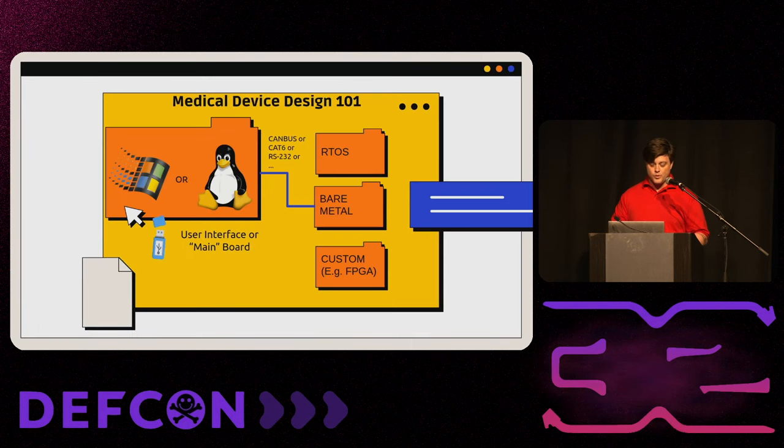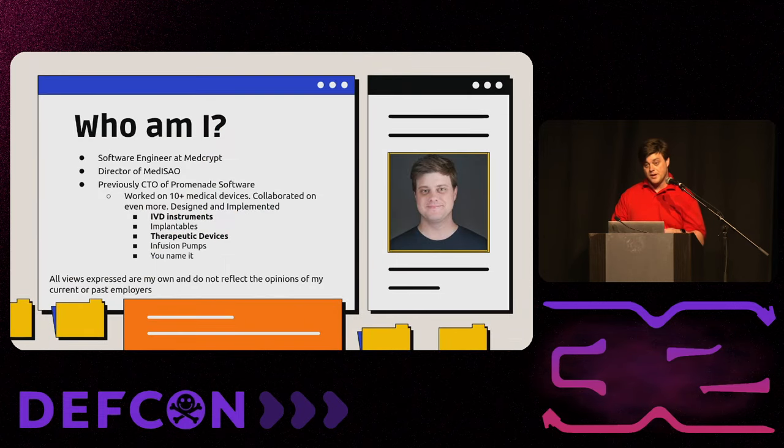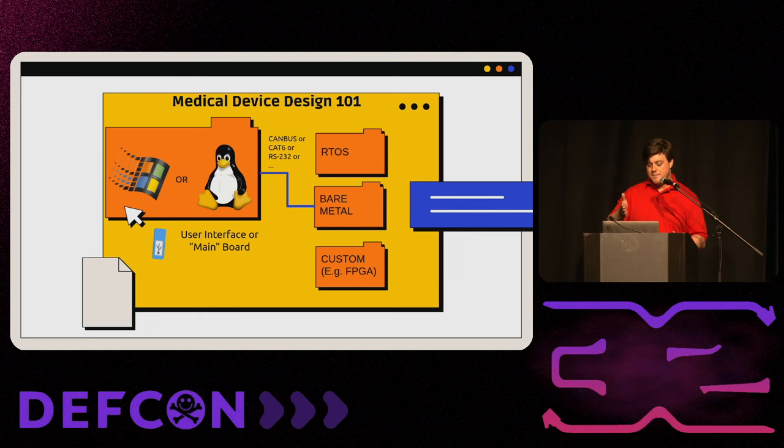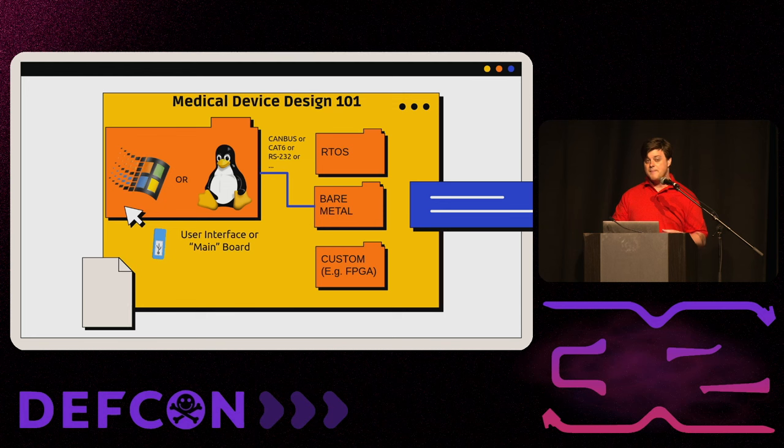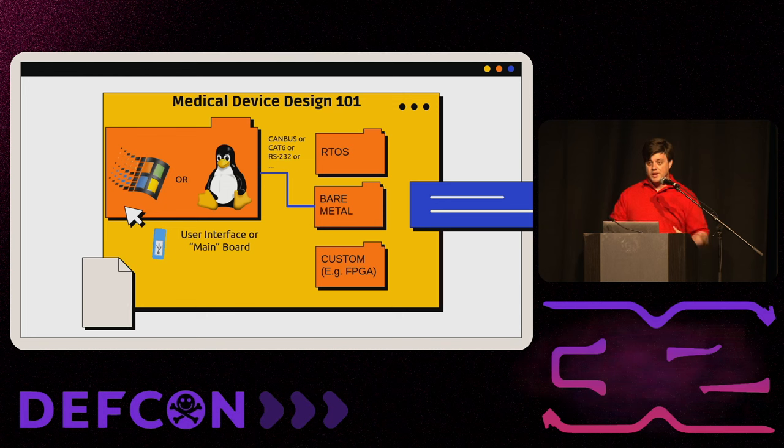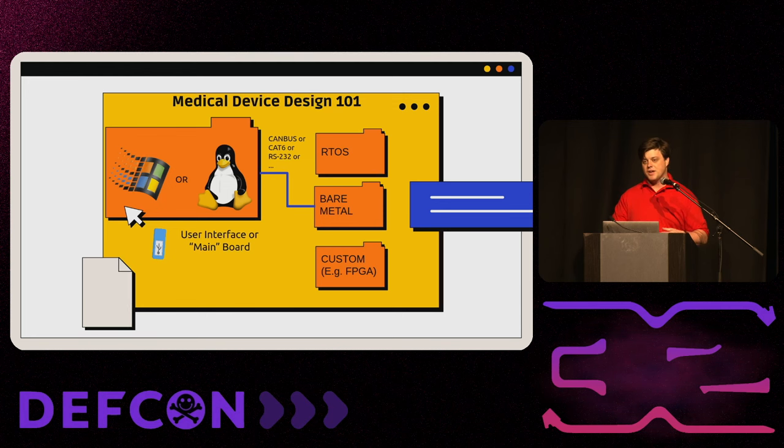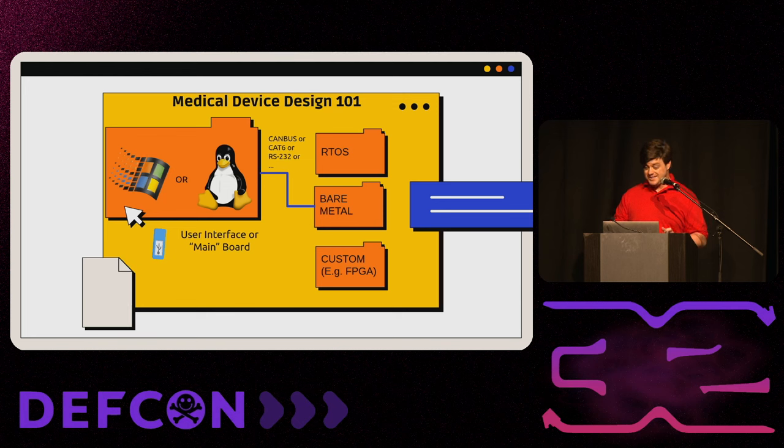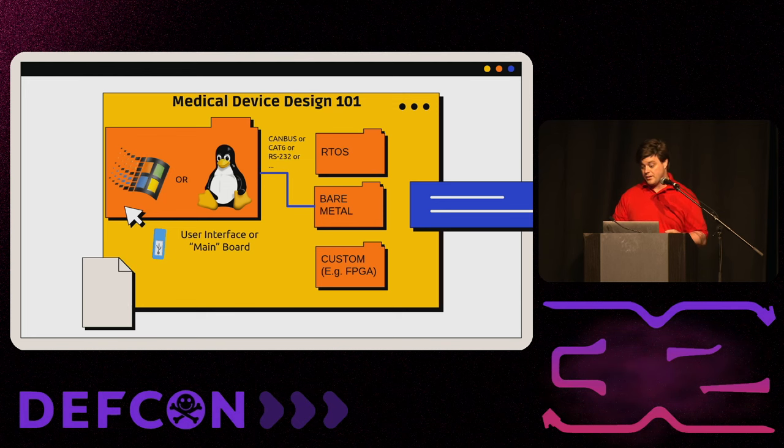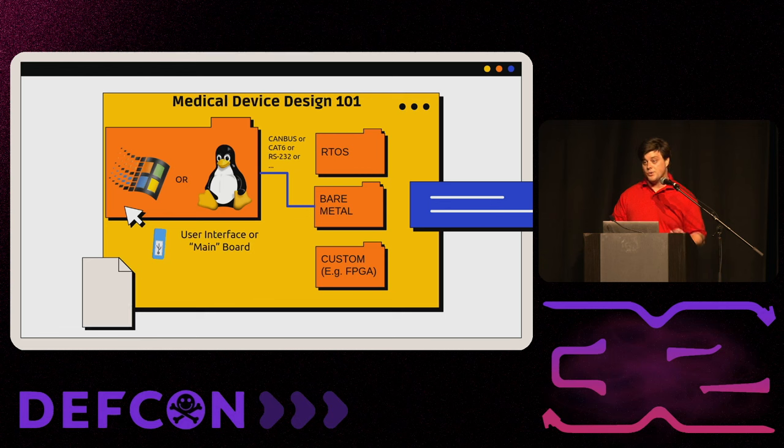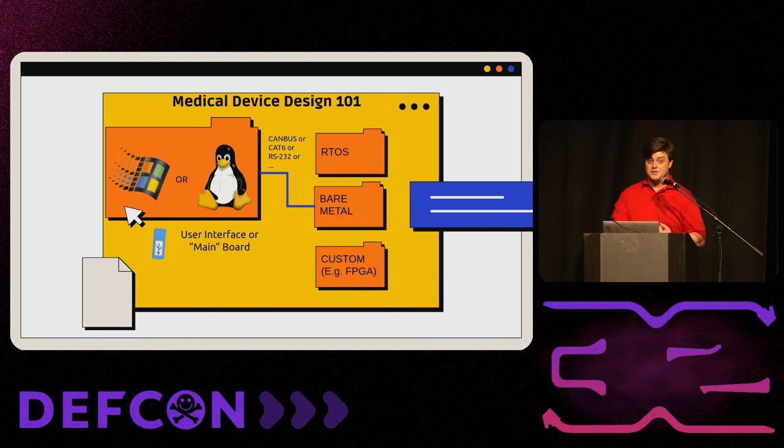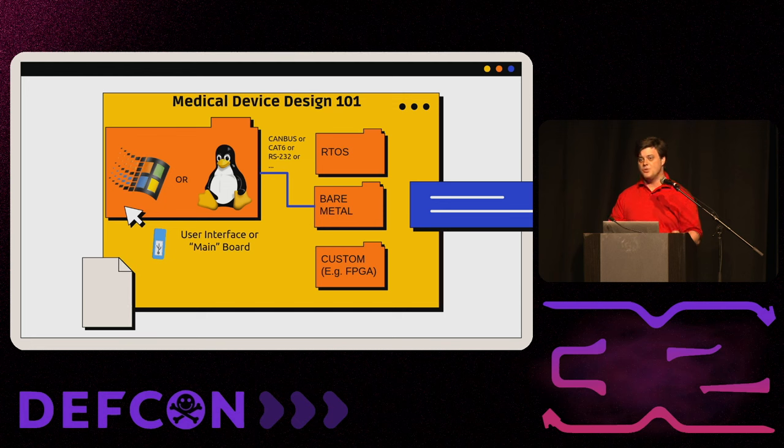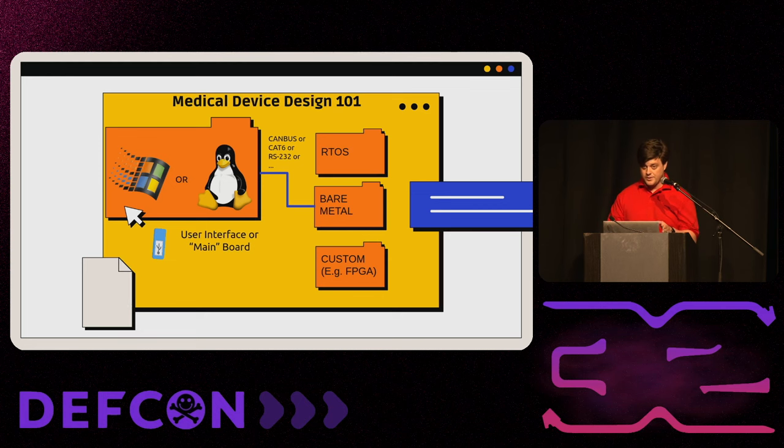Medical device design 101, especially on those bolded ones, IVD or therapeutic devices in a hospital setting or lab environment. Typically, you're going to have the embedded board that is going to be doing the medical thing. That's going to be running on something very important, like an RTOS. It's going to be bare metal. You're going to have a custom FPGA because it needs to be time critical. However, for anything that has a user interface more complicated than maybe a couple buttons, you're going to have a main board or user interface board that's typically running Windows or Linux. These are PCs that are connected via CAN bus, CAT 6, RS-232 to the thing that's actually doing the medical thing. If you can own them, you can pretty much own the device.